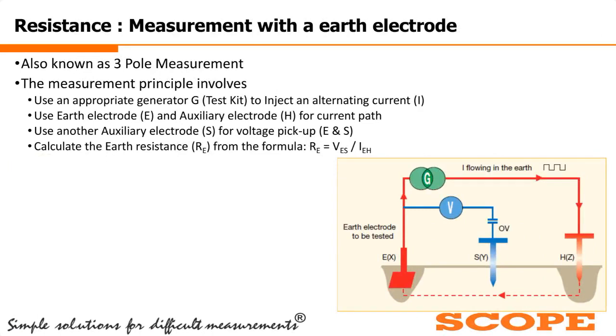So that's why the three-pole measurement method was developed, and it is widely used. In this three-pole measurement method, a current generator generates current pulses at a certain frequency. This current generator will inject an alternating current I, and for this method, the earth electrode to be tested will be connected to the E terminal of the instrument.